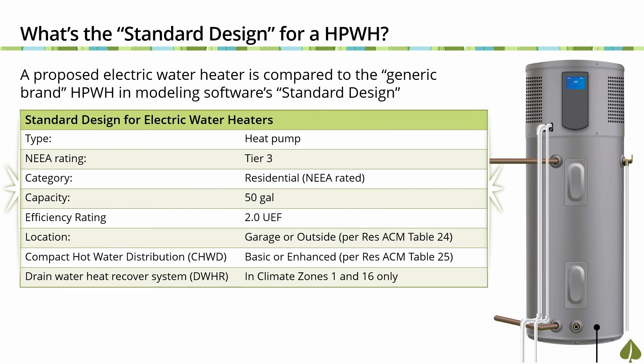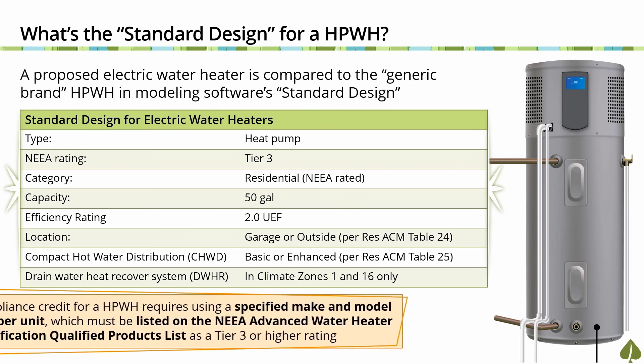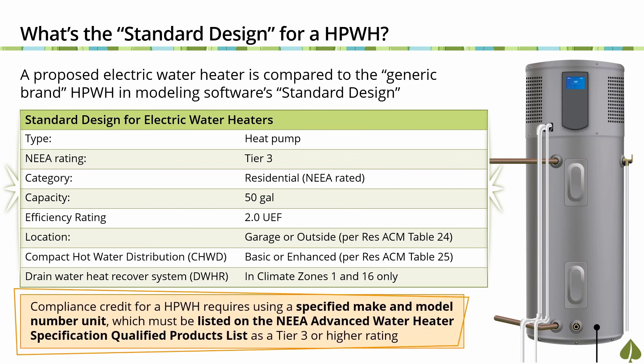Refer to Table 25 in Chapter 2 of the Residential ACM Reference Manual. When the project is located in climate zones 1 or 16, the standard design for a heat pump water heater also includes a drain water heat recovery, or DWHR, system. To receive a compliance credit for a heat pump water heater requires using a specific make and model number unit which must be listed in the NEEA Advanced Water Heater Specification list of qualified products as a Tier 3 or higher rating. Understanding what sets the standard design for a DHW system is important for making recommendations to meet or exceed the energy code requirements.